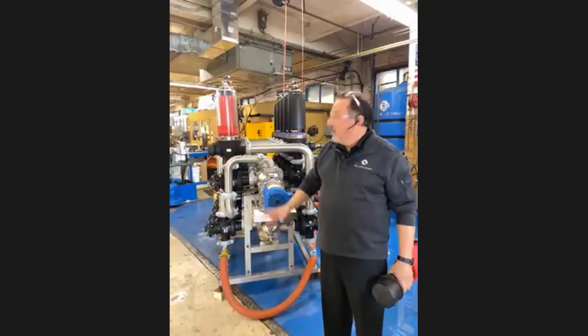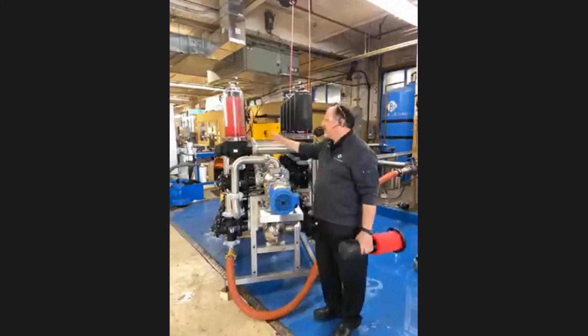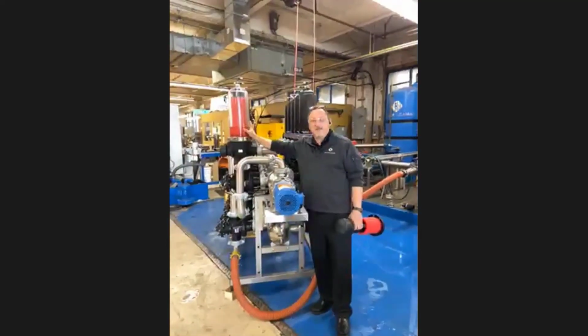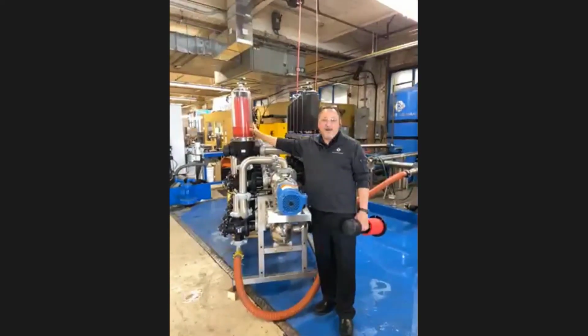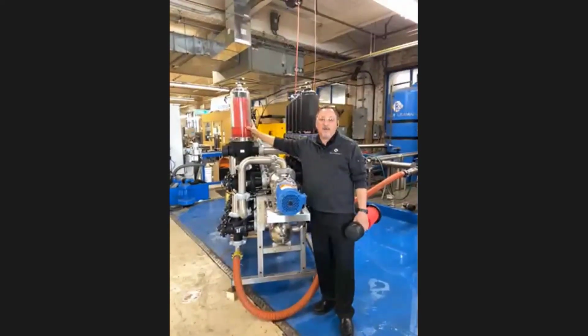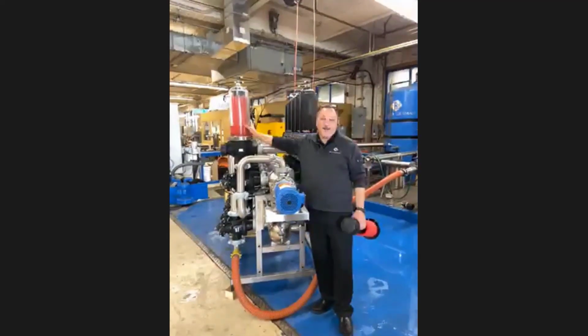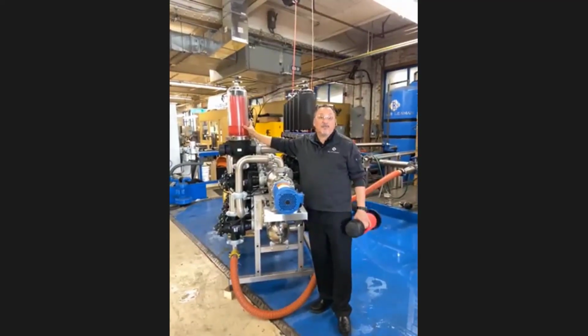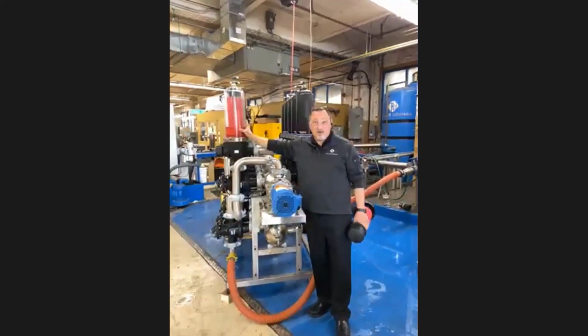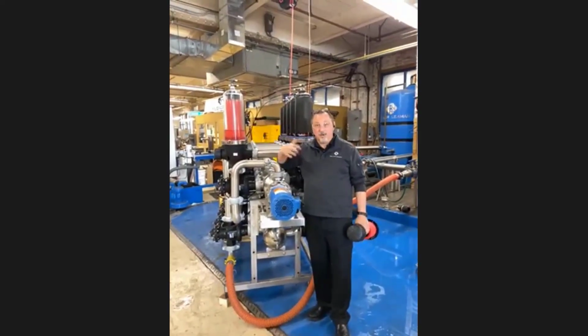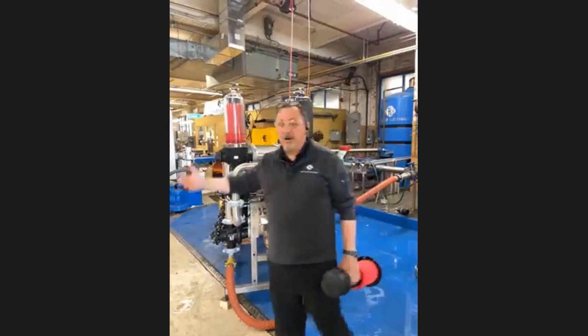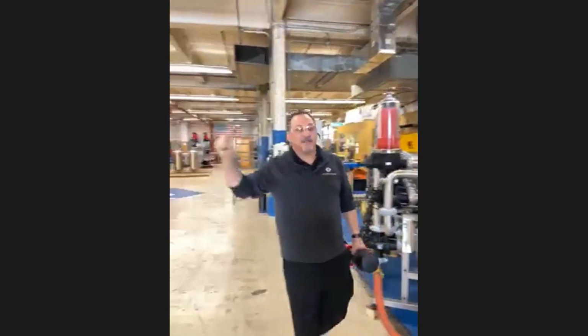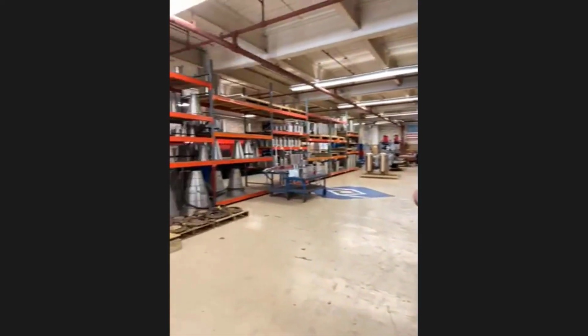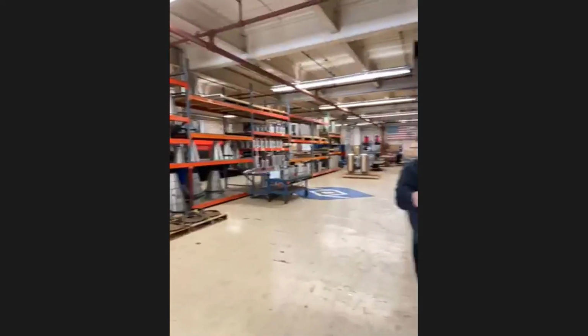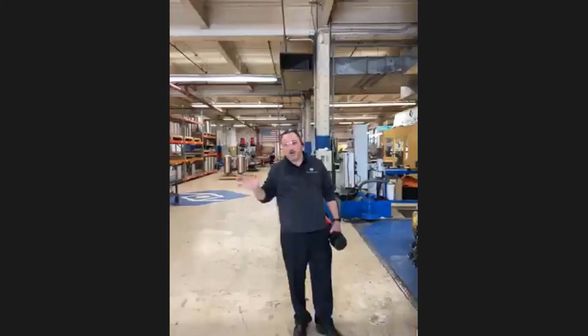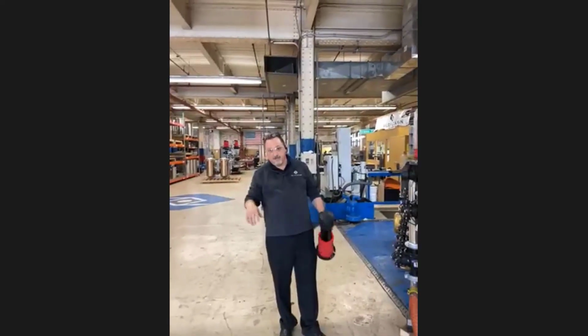It can keep up with it because each pod at 15 seconds per pod is only going to backflush 12 gallons of water. So as a 10-pod system, it's only going to backflush 120 gallons of water. For a 1,000 gallon per minute system, that's pretty remarkable. Whereas a sand filter would be around 3,000 gallons of water. So you can see the big difference of water use. And everybody's green these days. Our products are all green. Our Thompson strainer has less than 1 PSI pressure drop across it, very green filter. Our Turbo Disc uses much less backflush water than sand filters or other types of filters out there.